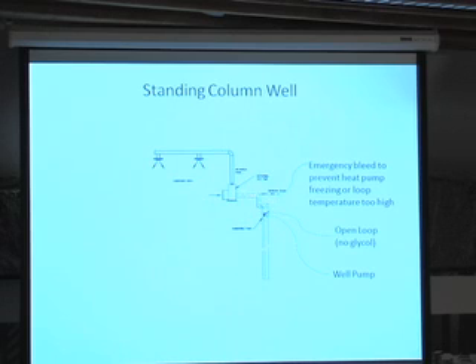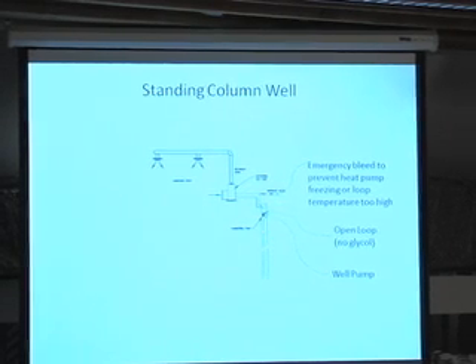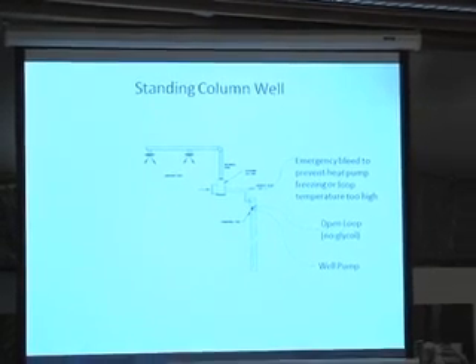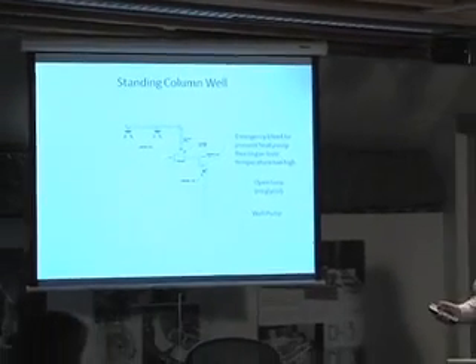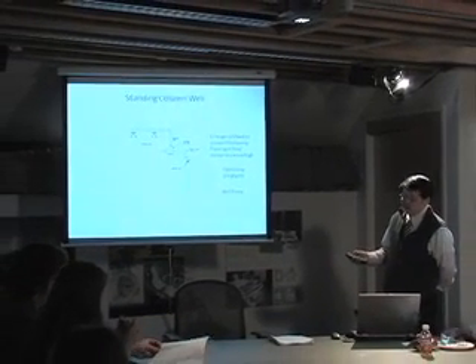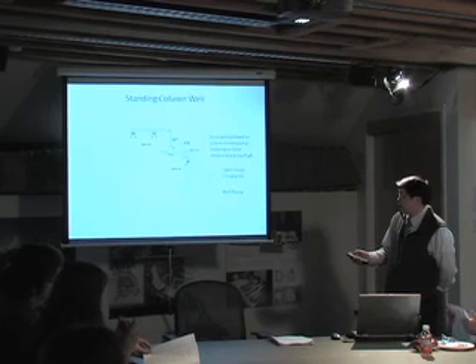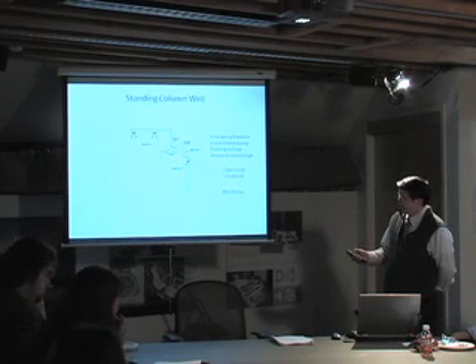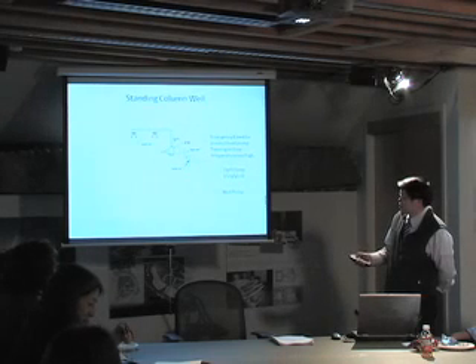And for this type of system, you have an emergency bleed. For example, when you're doing heating in the winter, you're pumping water from the well and extracting heat out of it. So the water gets colder and colder until it reaches an equilibrium point. And that temperature could be very low. If it becomes below freezing point, that's a problem. So you have an emergency bleed here. If the temperature gets too low, you bleed some water out, and then the water is going to make up from the surrounding ground, which is warmer.